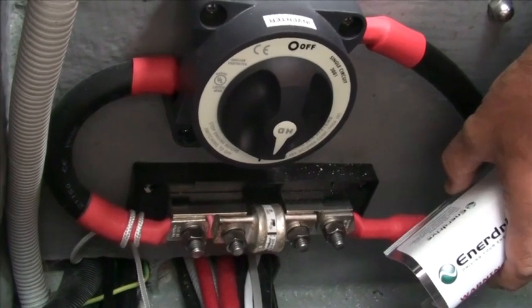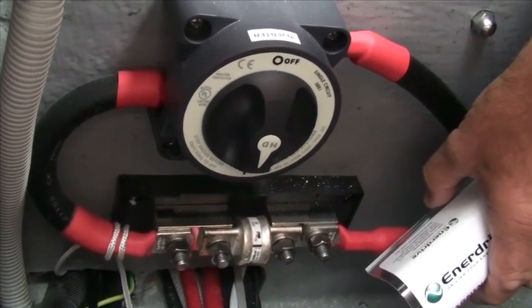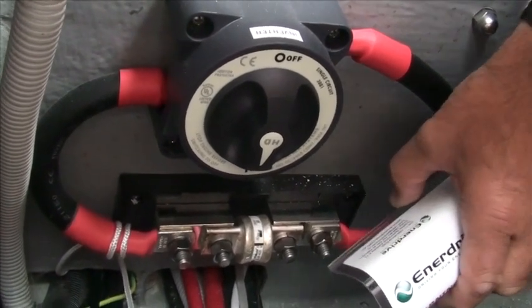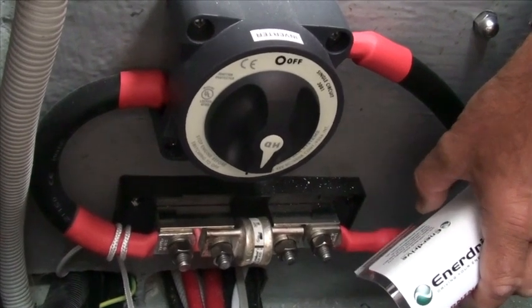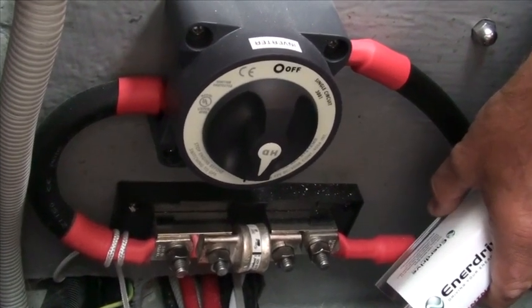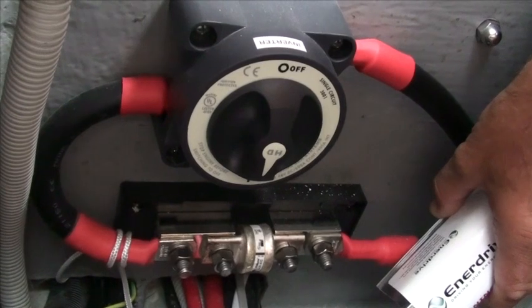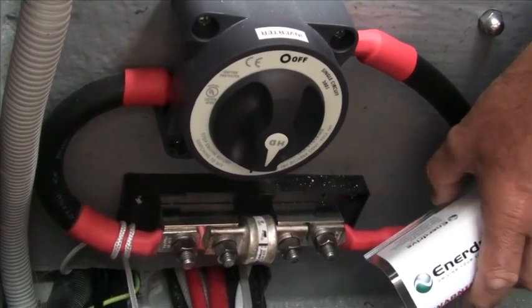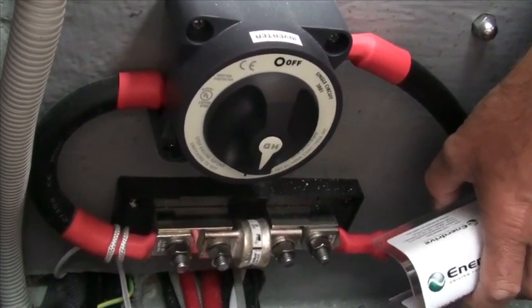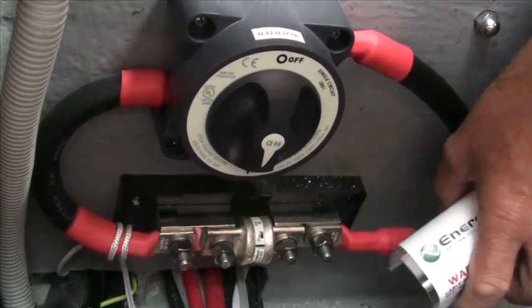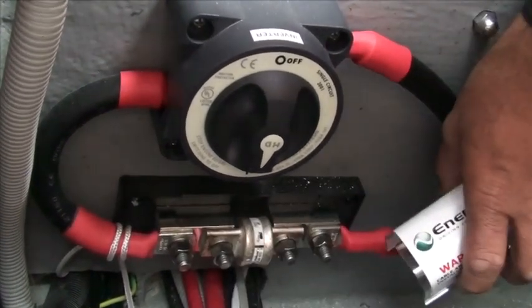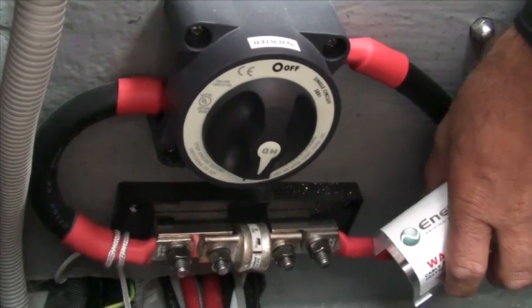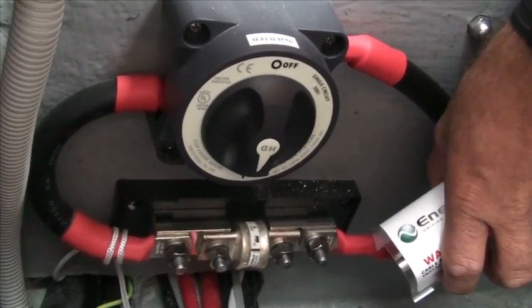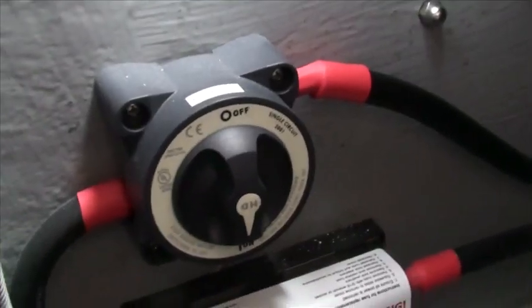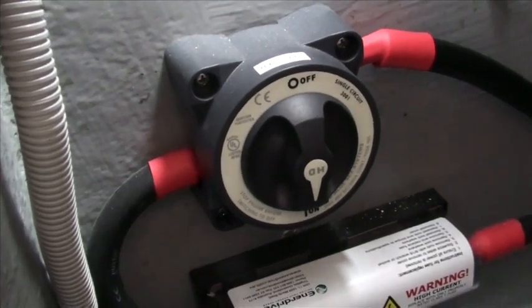If it blows, you've got a major problem with the inverter, or someone's done something at the batteries when they're charging is running. So I don't have a spare that I can... No, I can organise you a spare if you like. In a worst case scenario, you can just join the cables together, if you know for sure that you've eliminated the cause of blowing the fuse, to isolate the inverter from the batteries.